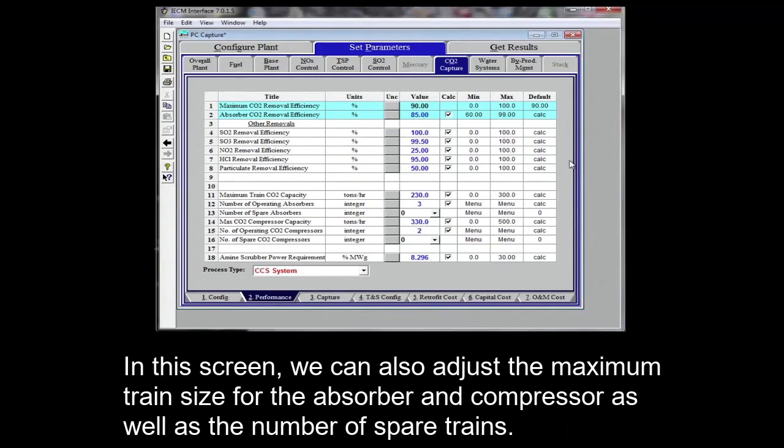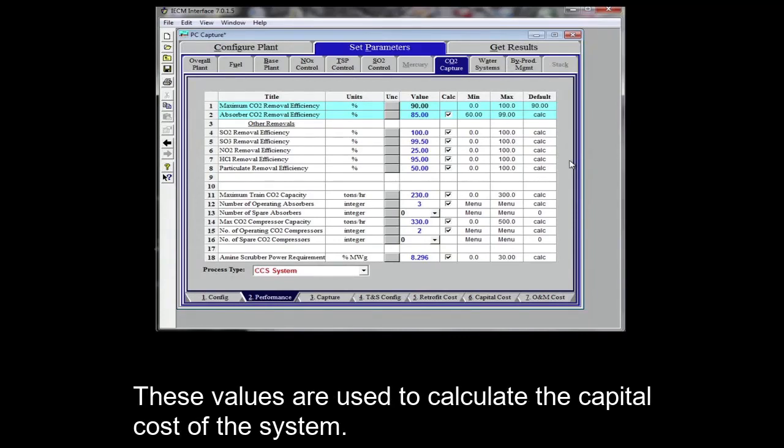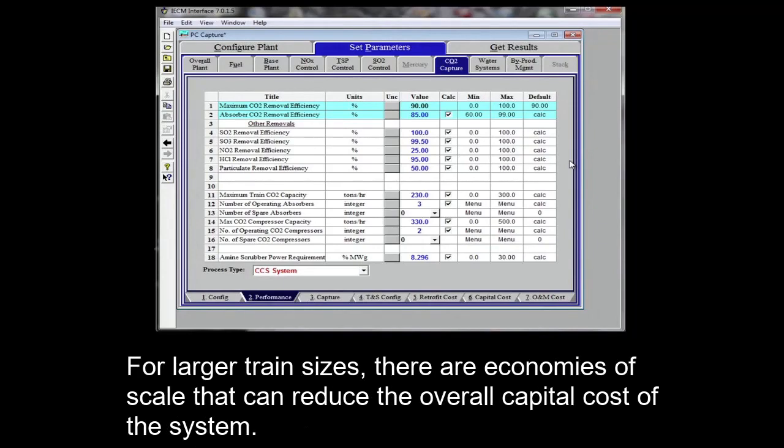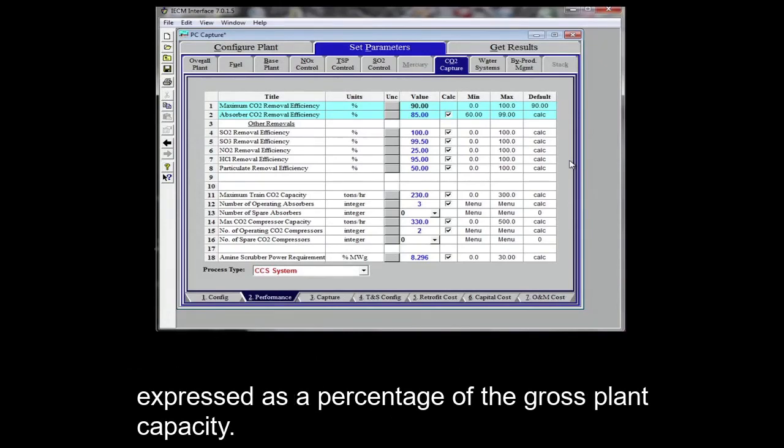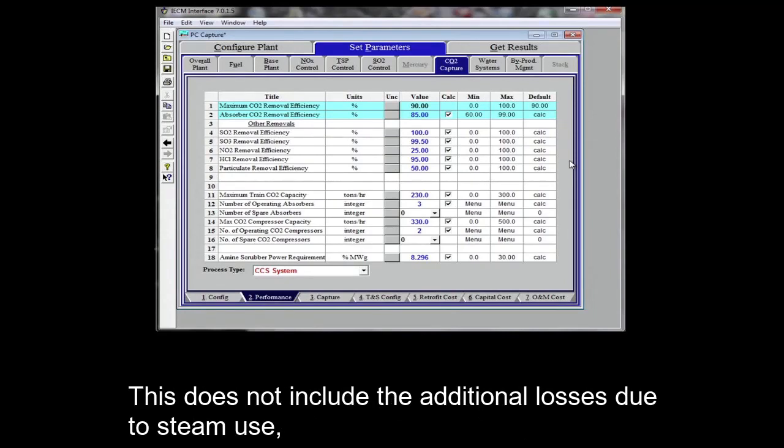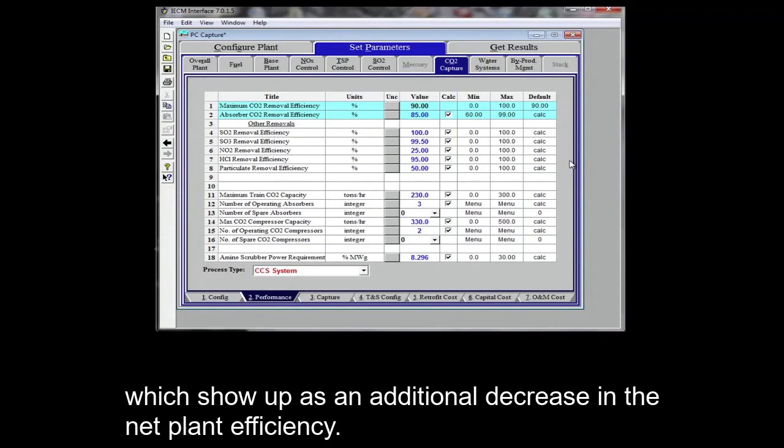In this screen, we can also adjust the maximum train size for the absorber and compressor, as well as the number of spare trains. These values are used to calculate the capital cost of the system. For larger train sizes, there are economies of scale that can reduce the overall capital costs of the system. The final line on this screen is the electrical power requirement of the system, expressed as percentage of the gross plant capacity. This does not include the additional losses due to steam use, which show up as an additional decrease in the net plant efficiency.